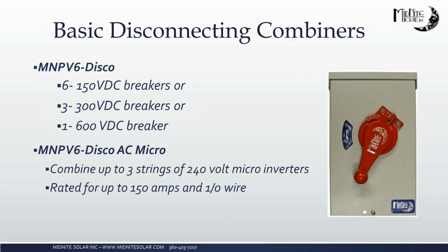The PV6-Disco AC Micro. That's an interesting one, and micro really shouldn't be in there. If you look down below, you'll see it's got 150 amp bus bars. It'll take up to a 1/0 wire. So this is truly an AC combiner. It'll take 3 strings up to 50 amps per string at 120/240 volts and output a single output up to 150 amps. So you could have 3 pretty big grid tie inverters and combine them into this almost like a recombiner to go back to your utility feed, or you could use it for 3 strings of microinverters at 20 amps per string. So it's a pretty versatile AC combiner as well.